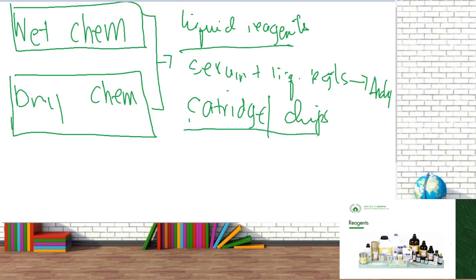In dry chemistry, there is a chip wherein the serum will go inside the machine where you are going to feed your sample. There are tiny tubes or what we call cuvettes that will aspirate your sample, and these transferring cuvettes will transfer your sample, your aliquot.